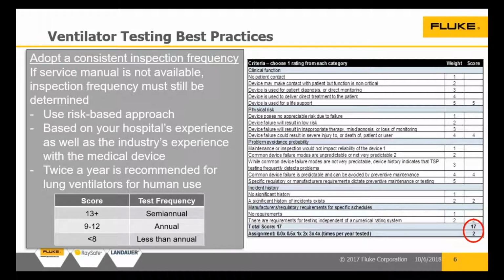In ventilators, I absolutely want at least twice a year. But keep in mind that there are still many ventilators out there whose frequency of inspection is not based on the calendar. What's it based on? Use hours. Use hours, right. And there are several different levels of maintenance for several different subparts of the system that are based on that use hour. For example, a compressor might be 10 to 20,000 use hours, whereas other parts of the ventilator that are critical and need to have some components replaced are going to be every 2,000 hours or so. So don't get trapped into thinking only of the calendar way of thinking about inspection frequency.